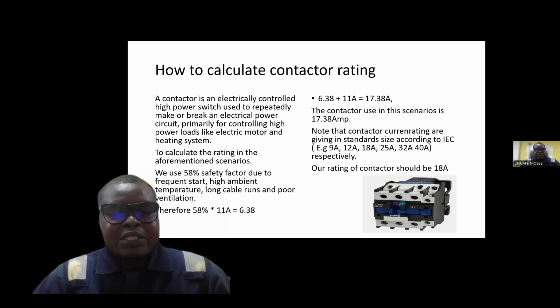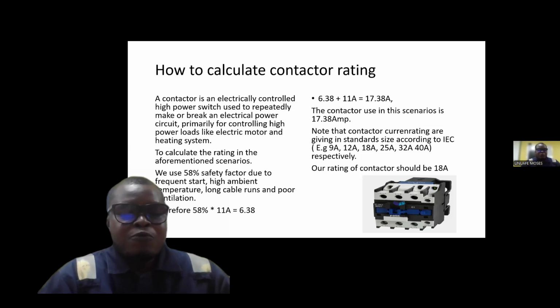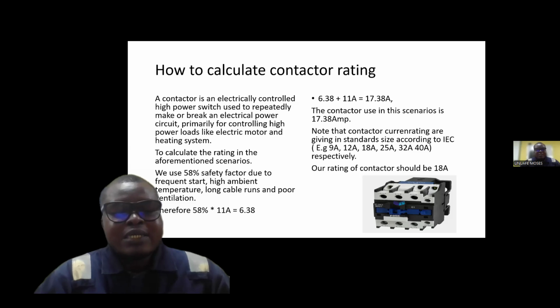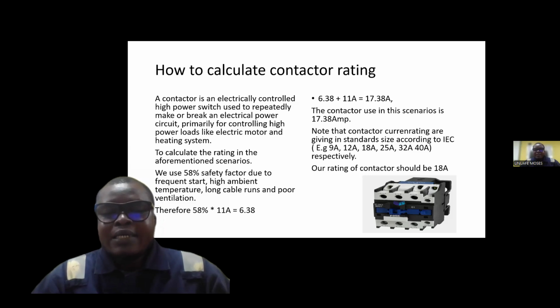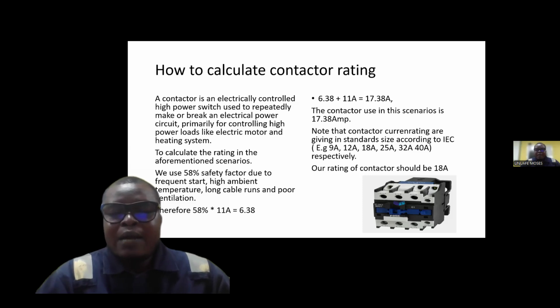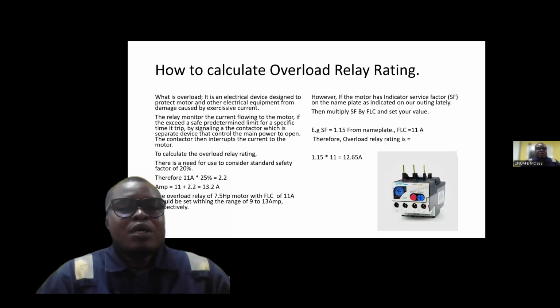So by considering that, 58% multiplied by our FLC, which is our full load current, is going to give us what? 6.38. And when you add 6.38 to our full load current, it's going to give you what? 17.38 amps. The contactor used in this scenario is now 17.38 amps. Remember that our contactor current, according to IEC, is rated in 9 amps, 12 amps, 18 amps, 25 amps, 32 amps, and 40 amps respectively. And our rating of contactor should be 18 amps because it's far closer to our ampacity, which is 17.38 amps.